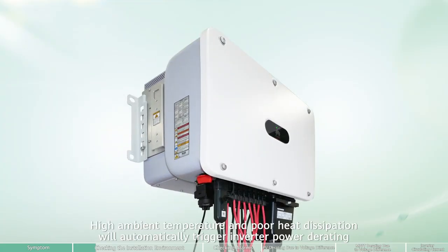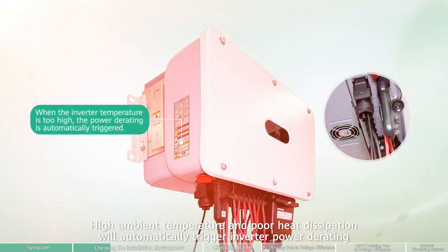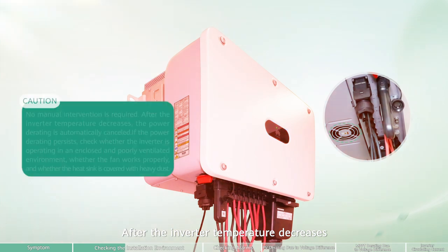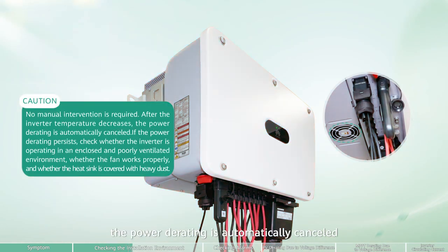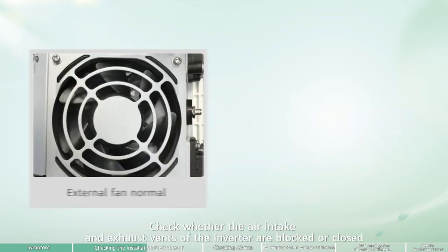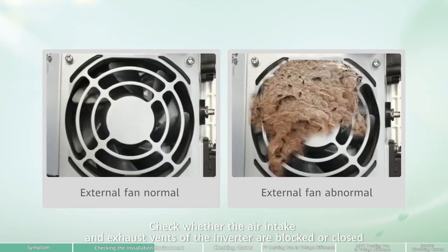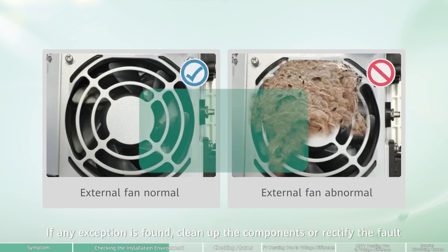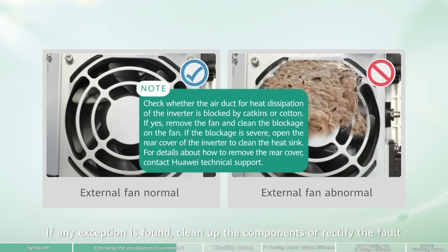High ambient temperature and poor heat dissipation will automatically trigger inverter power derating. After the inverter temperature decreases, the power derating is automatically cancelled. Check whether the air intake and exhaust vents of the inverter are blocked or closed. If any exception is found, clean up the components or rectify the fault.